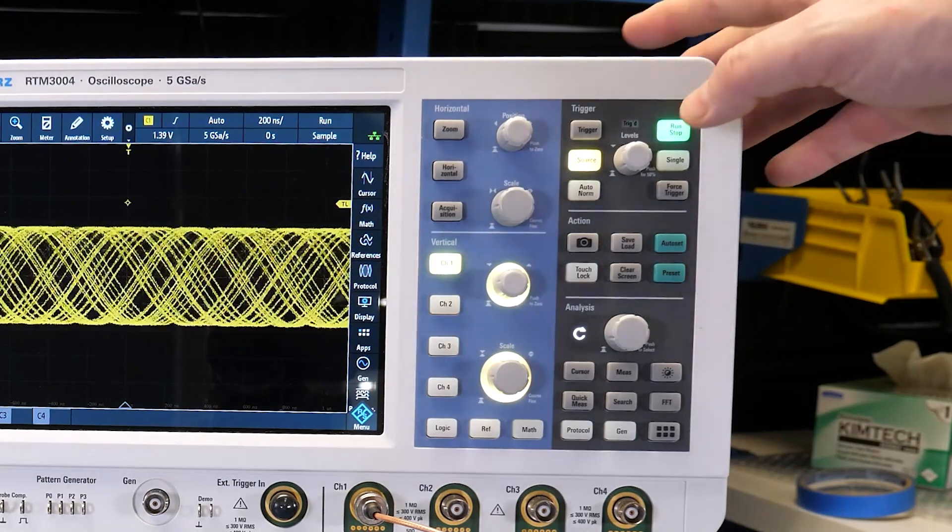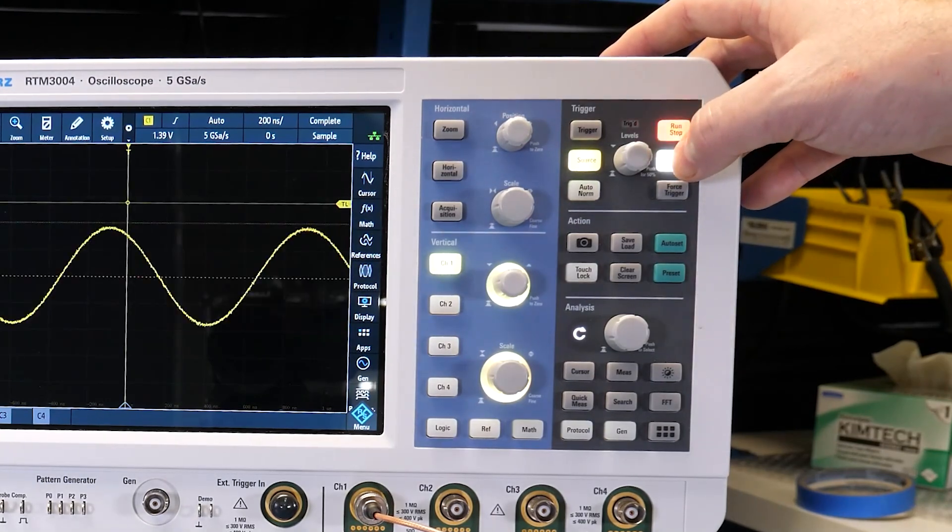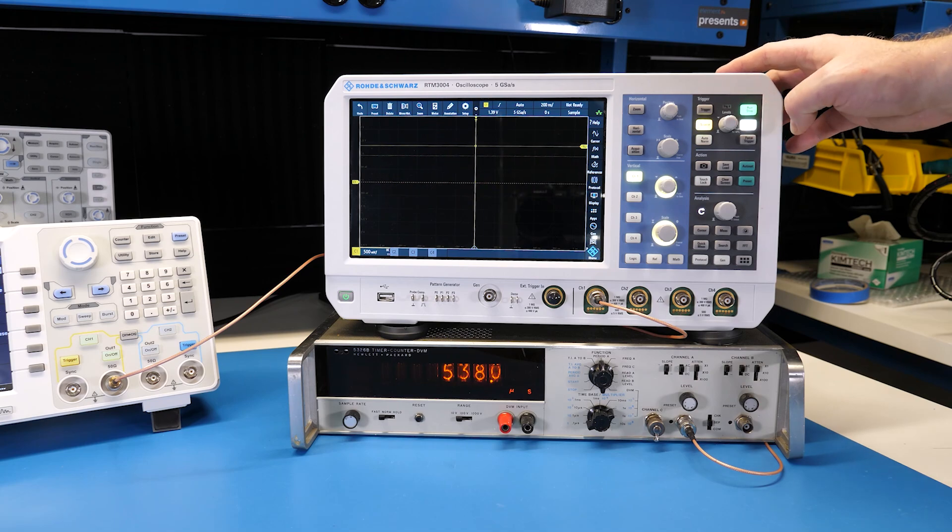By the way, some scopes have something called a digital trigger. The trigger system in these oscilloscopes monitor the sample data to detect events digitally. But either analog or digital works about the same for the purposes of this video in terms of using the triggers. Digital scopes have auto, normal, and single. Single is the most obvious of the three. The oscilloscope will capture a single acquisition each time you run the scope or press the single button.